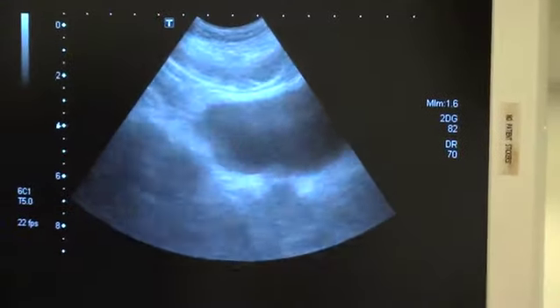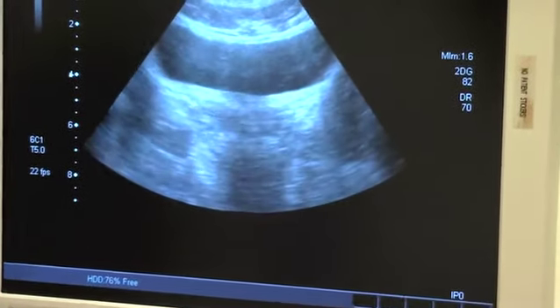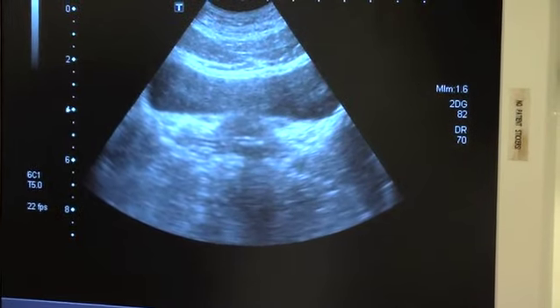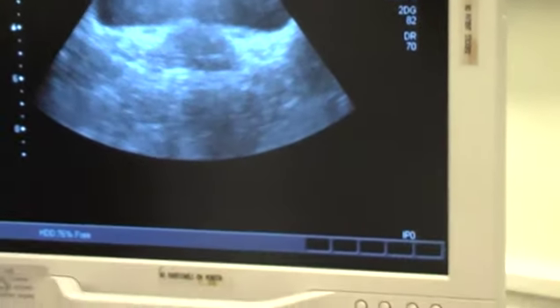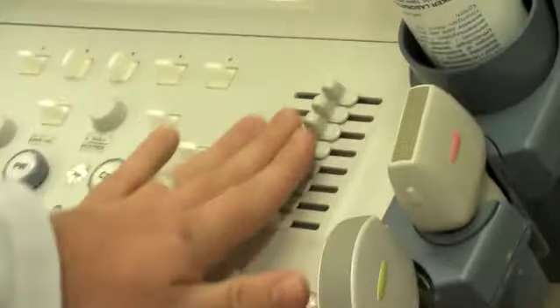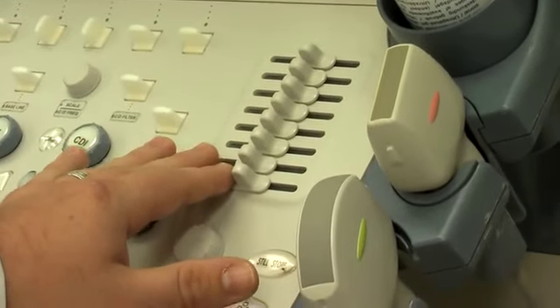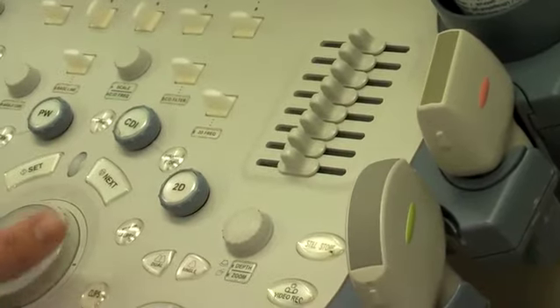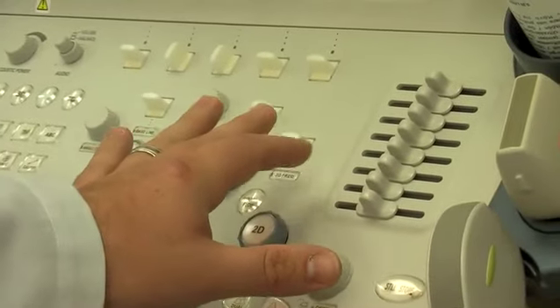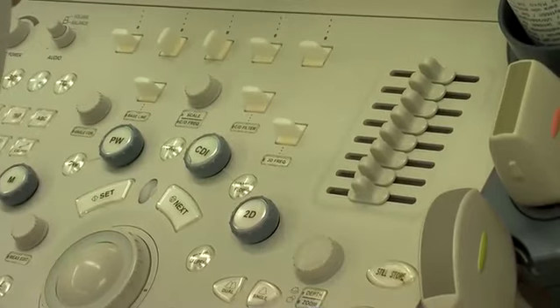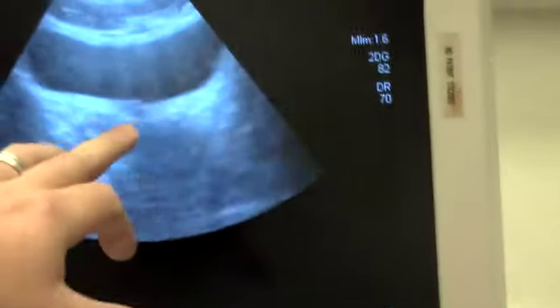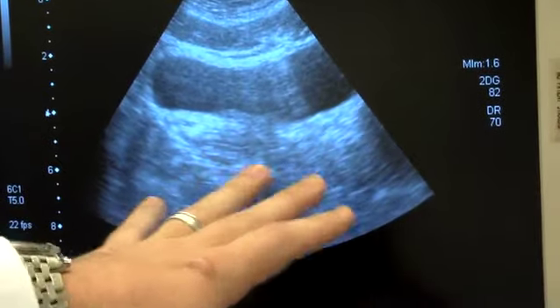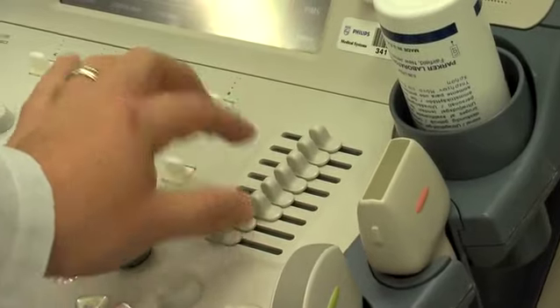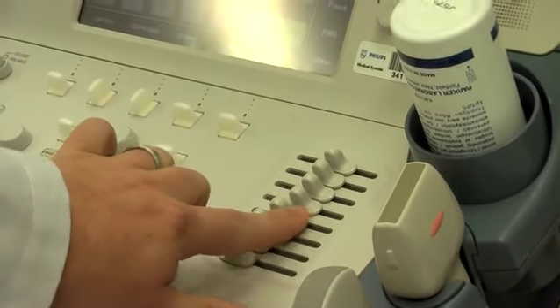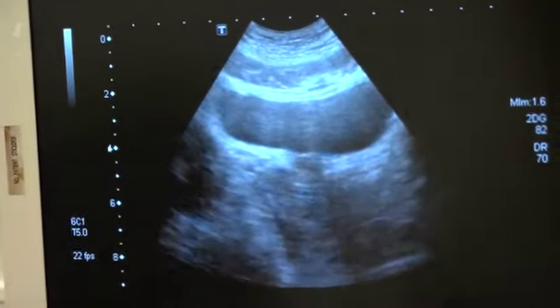Another thing I'll point out on the machine is a function called time gain compensation, or TGC. That's these things over here. What that does is, instead of the gain changing the brightness overall for the entire screen, that'll change the brightness at a certain level of the screen. So in this view, oftentimes because of posterior acoustic enhancement, the far field is much brighter than it normally should be. So you can turn down the gain a little bit by moving these buttons down, and it makes it less bright in the far field. Let me just show you. If I was to increase it all the way, it would make the far field really bright, but the near field normal.